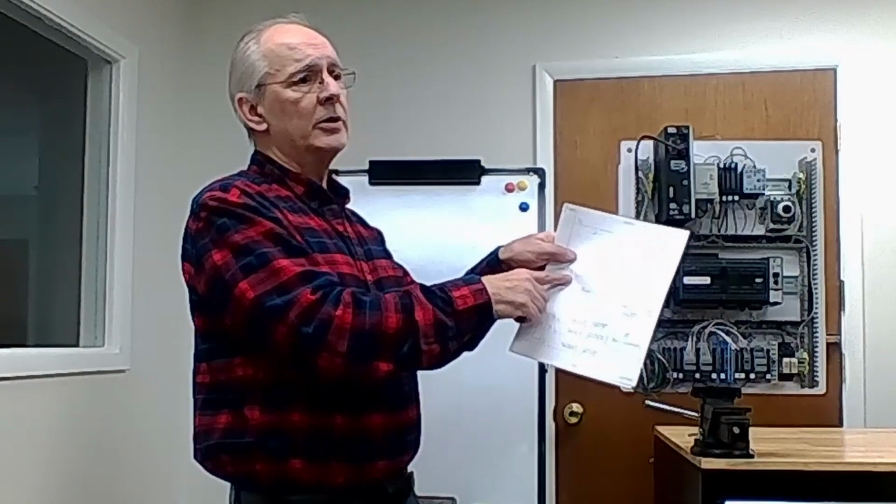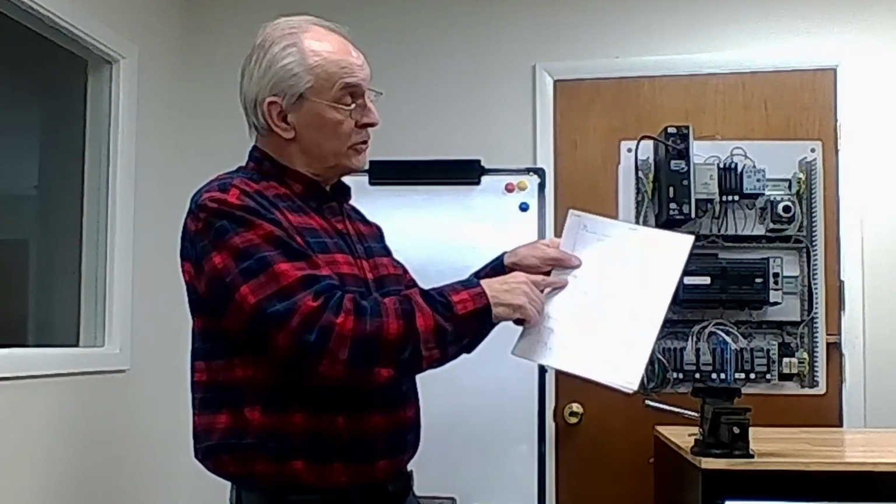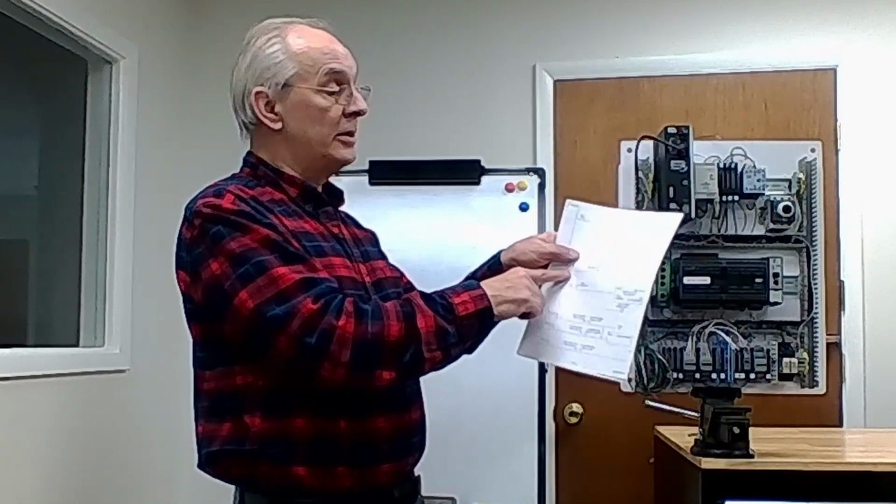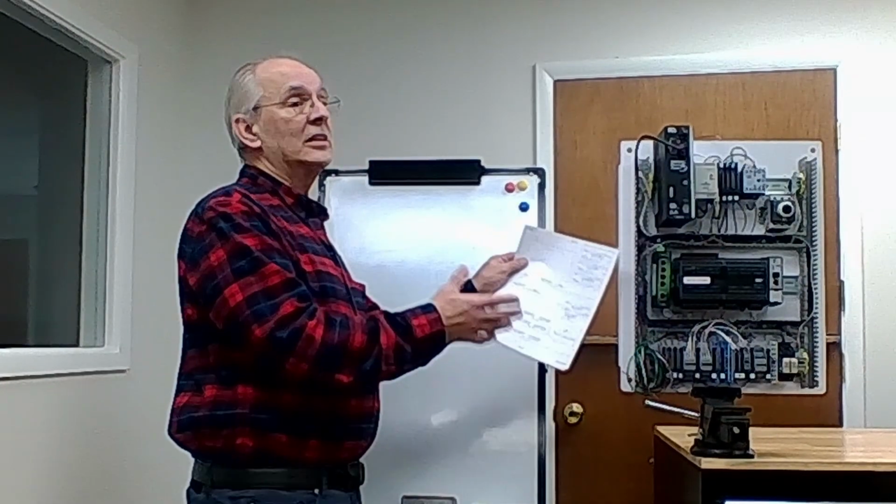So this is comparing a number to 0, saying if it's 0, then do something else, okay? Now, if this is actually 0, then this will be lit up, to indicate that yes, this rung is able to work. So you just go down the rungs looking for where it stops, okay? And that's how the troubleshooting works, and that's exactly the way you troubleshoot the wiring.